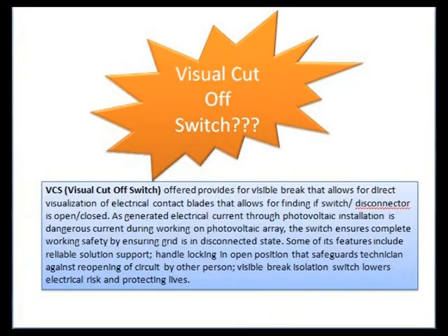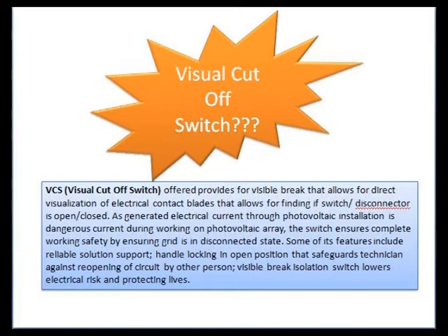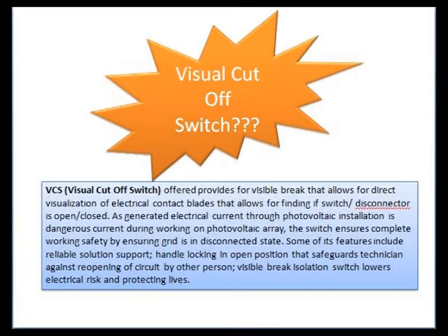The visual cutoff switch (VCS) provides a visible break that allows for direct visualization of electrical contact blades, letting you determine if the switch disconnector is open or closed. In short, VCS provides an easy indicator to the user that electrical blades or contacts are disengaged and electrical energy is now isolated. After applying VCS, one can safely work on the circuit or equipment. Generated electrical current in photovoltaic installations is dangerous, and during work in photovoltaic areas, the switch ensures complete working safety.